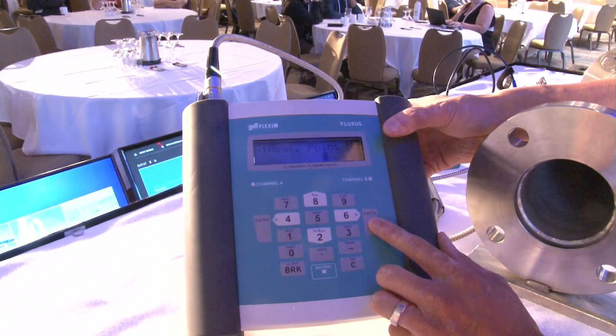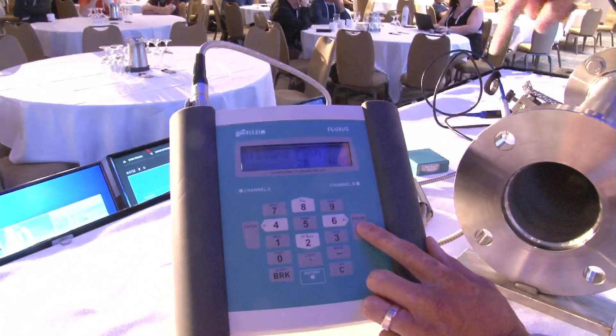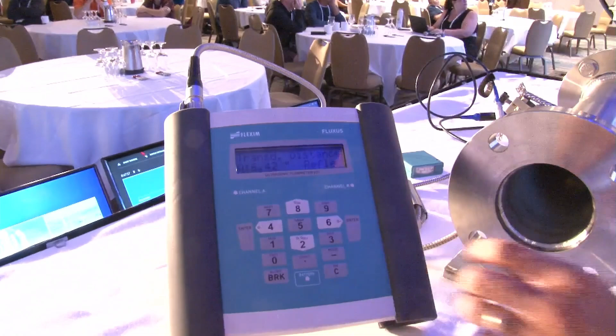Then what I'm going to do is go to the measuring portion. It's on channel A. Measuring point number, yes. There are 2 paths because we're going to do a bounce path, so have it on the same side of the pipe. It's telling me my transducers need to be roughly 6.5 inches apart.